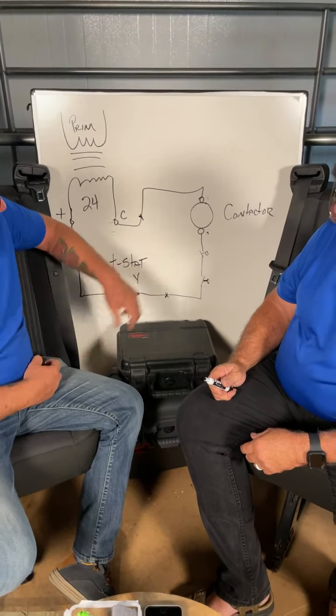So when you're going from R to Y and you're reading 24 volts here, it's because you have this coil of wire, so you're getting the back feed from common through the coil of wire coming back to Y. So you can kind of see that. You're going to get a 24 volt reading, but this coil's not pulling in, because you don't really have 24 volts here until you close this switch. Once this thermostat closes, then you'll have 24 volts on this side, and this should return back to your common.